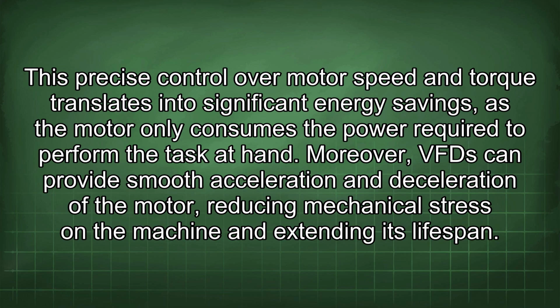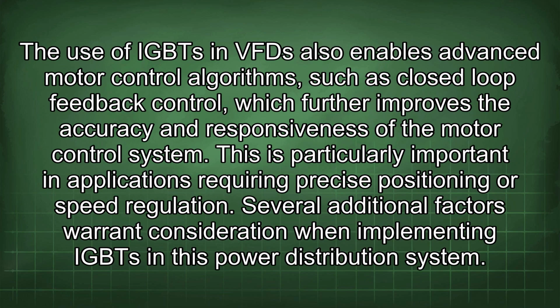Moreover, VFDs can provide smooth acceleration and deceleration of the motor, reducing mechanical stress on the machine and extending its lifespan. The use of IGBTs in VFDs also enables advanced motor control algorithms such as closed-loop feedback control, which further improves the accuracy and responsiveness of the motor control system. This is particularly important in applications requiring precise positioning or speed regulation.